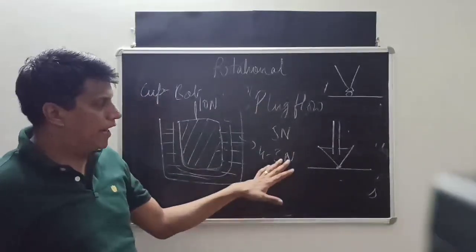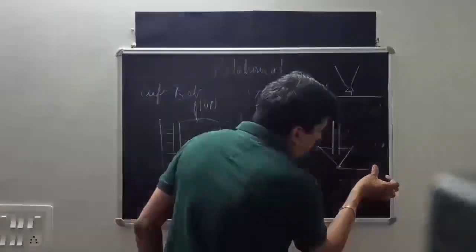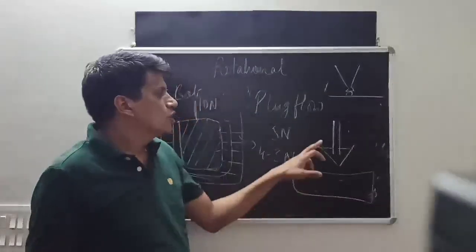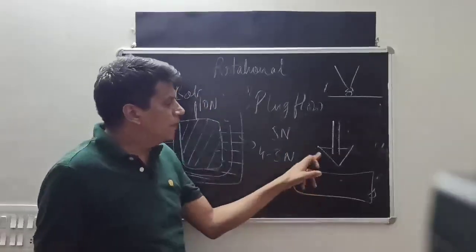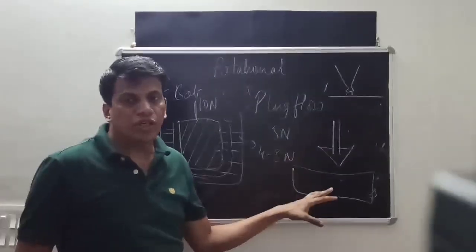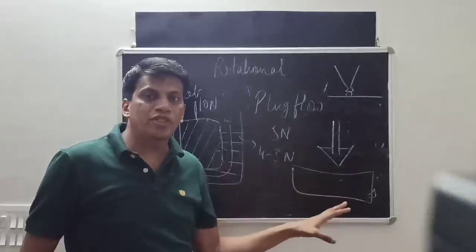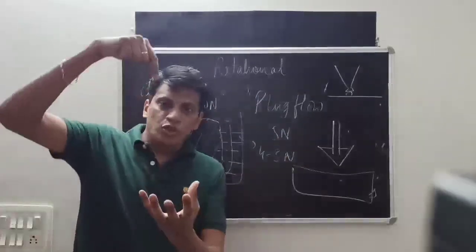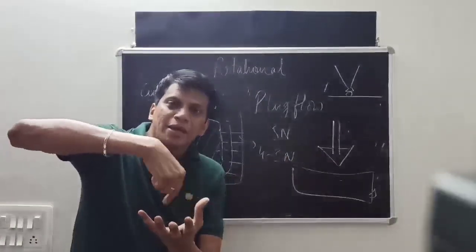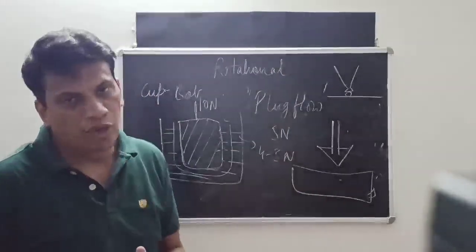Penetrometers are an advanced form of cone and plate viscometers. They look similar but have no plate — only a cone. This cone can penetrate semi-solid or solid materials and move inside. Penetrometers are spindles with various cone shapes used to determine the viscosity or rheology of semi-solid materials like ointments or creams, where other equipment does not work. They penetrate, rupture, and collect the rheometric data.